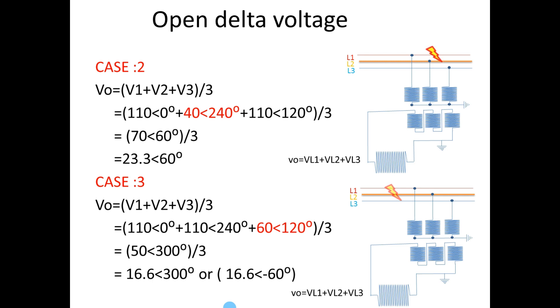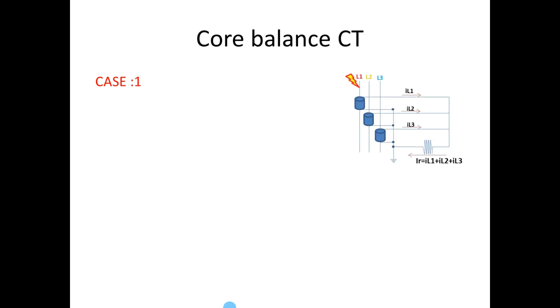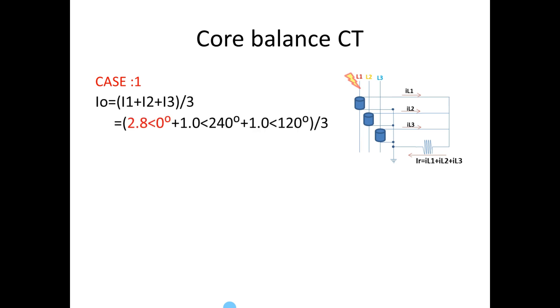Now we can go for calculating the current magnitude and angle during the fault condition. For Case 1, considering the fault on R phase, the R phase fault current is 2.8A. The I0 current we get is 0.6A at 0 degrees. We will note down this value.